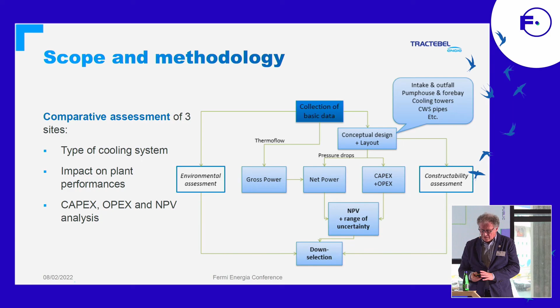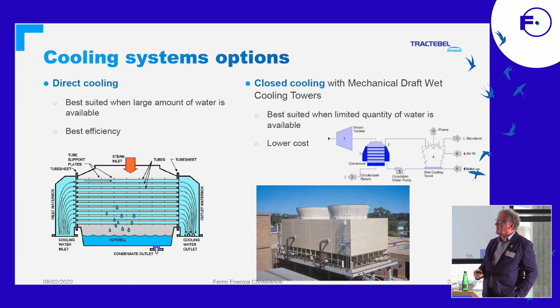Then there's closed-loop cooling with mechanical draft wet cooling towers, which are low-rise cooling towers in a battery, several of them. That's the best suited solution when there's a limited quantity of water available, and it's also lower cost. It still requires a source of cooling water, but the makeup flow is like 30 to 40 times less than direct cooling, so it has a lesser impact on the environment or the water source.